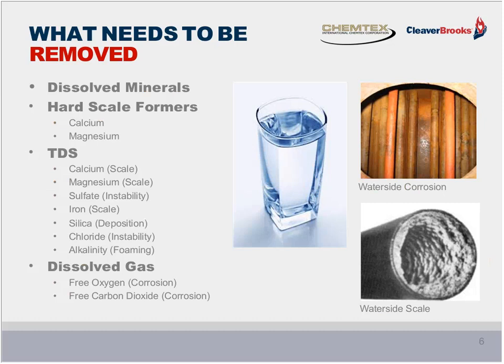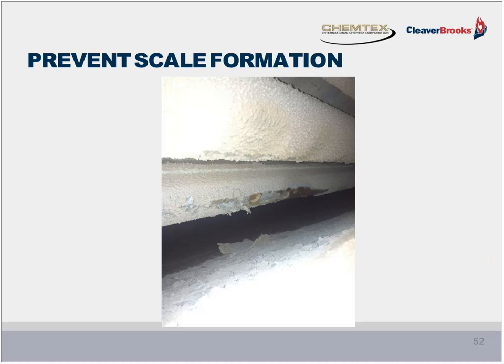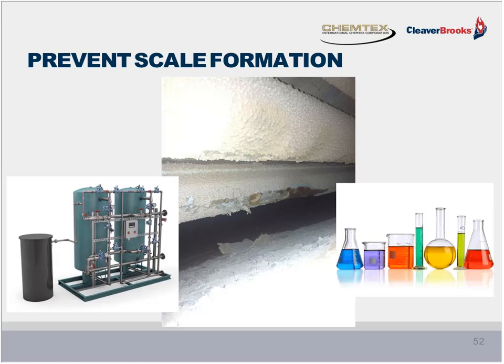All right, we're back to the impurities in the water, which can affect the boiler and connected system. And we just talked about the various dissolved salts, which can cause water level problems. But as you know, and what we talked about last month, is that these particular dissolved salts can be scale formers too, which could cost us downtime and repair costs. And that's what you see here. And as was mentioned before, the remedy is a combination of water softening and chemicals.